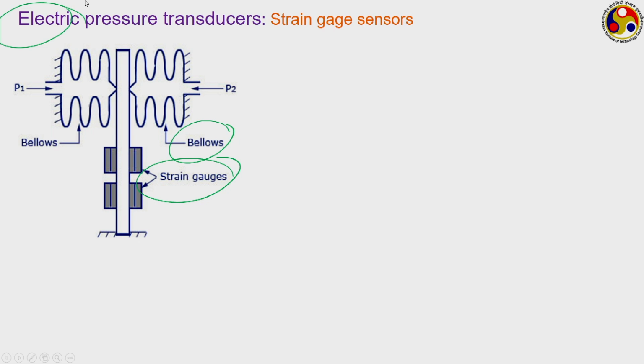Strain gauges, like we have already seen, though they are strain measuring instruments, generally find application in any kind of measurement. We have already seen it for force, and we are seeing it here for pressure. We shall also be seeing similar applications for temperature or similar other measurement devices, more as a secondary application, that is, some deflection is happening and then the strain gauge is picking up that deflection to give you a voltage output, which can subsequently be calibrated or related to the primary input, like force or pressure in this case, or maybe temperature or flow in subsequent discussions.